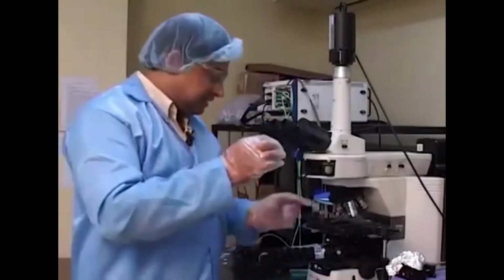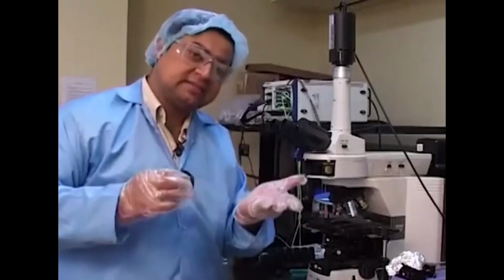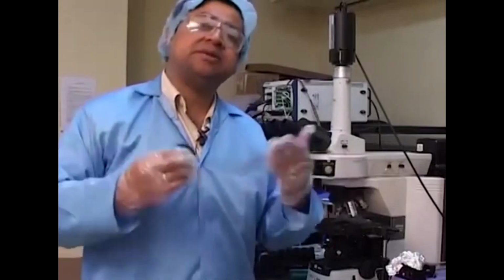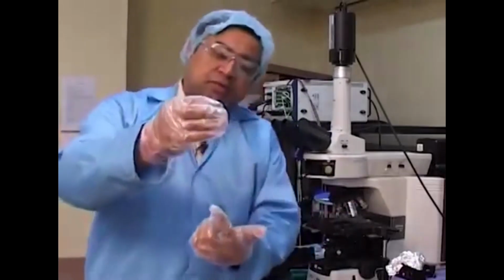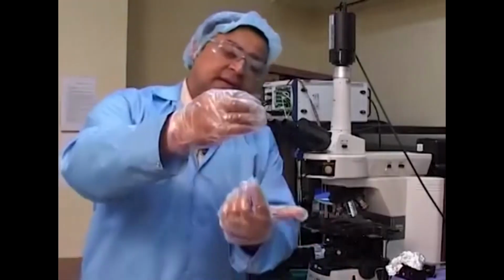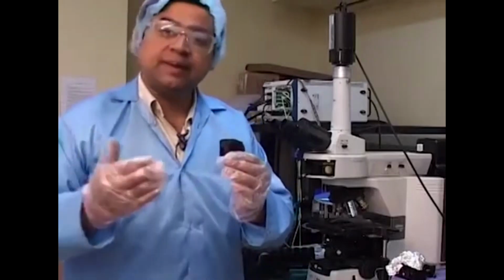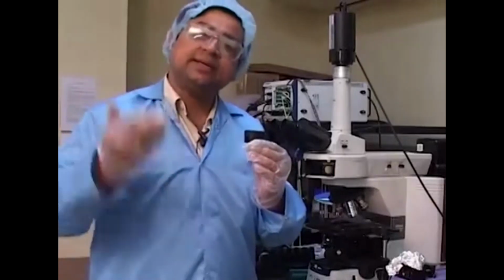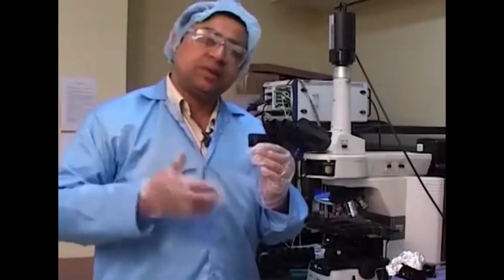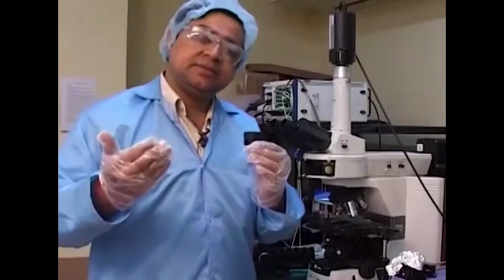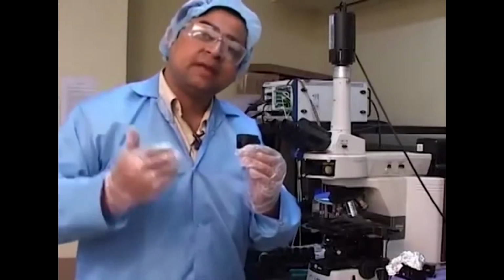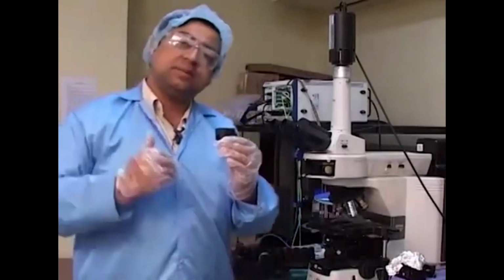So essentially when the light strikes the sample surface and there is a fluorophore, there is an emanation of a certain frequency, which is the emission frequency of the particular fluorophore. Now, this light would come back through the objective and hit the mirror, and here, as you see, the dichroic does its job again. In this case, because of the Stokes shift, the wavelength that is generated by the fluorescence is on the higher side. So suppose we have a fluorophore which generates an emission in the range of 620 nanometers, which is above the 590 cutoff that's provided by the dichroic.